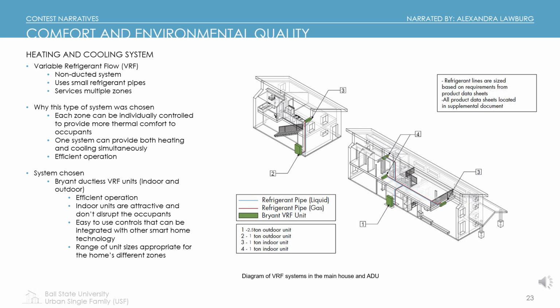Because the ERV system doesn't provide heating and cooling, a separate system is required to meet those needs. For this, we chose a variable refrigerant flow system, or VRF. VRFs can control multiple zones within a home individually and can even provide heating to one space while providing cooling to another. This type of system provides the best control for occupants and can greatly improve their comfort in the home.